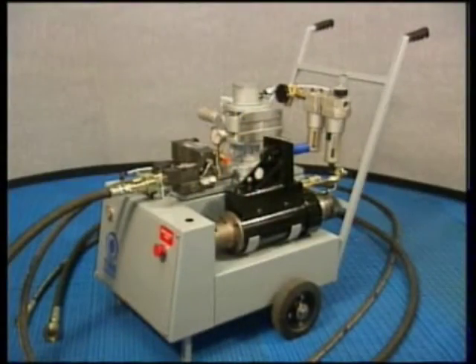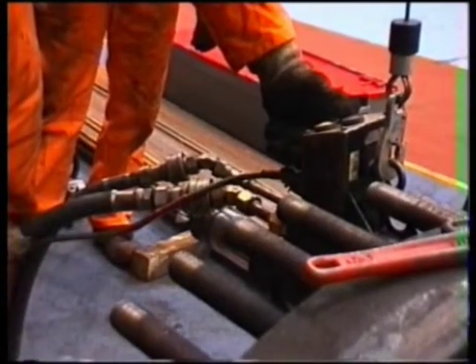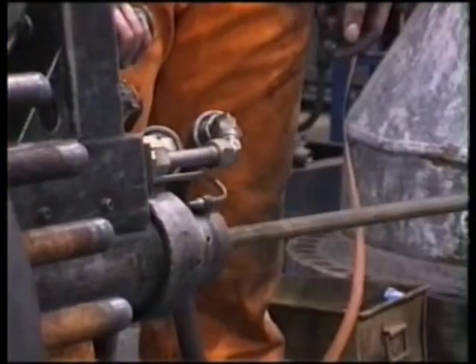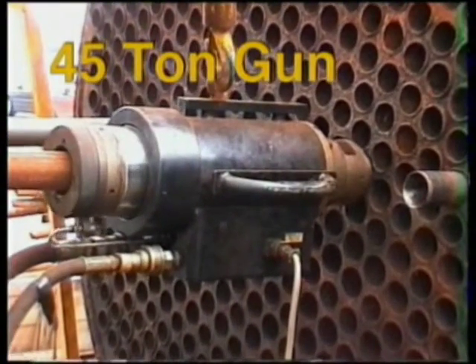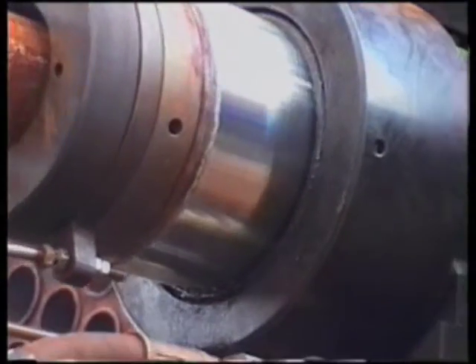The 15,000 series is supplied complete with quick release hose assemblies, a 24-volt control umbilical, and can be used with any of our range of pulling guns. The 15-ton gun for light-duty, high-speed work on tubes of outside diameters from 3/8 of an inch to 1 inch — for example, condenser work. The 30-ton gun for all tube sizes from outside diameters of 3/8 of an inch to 1 and a half inches continuously through the gun, and up to 3 inch stub pulling. The 45-ton gun for tube sizes up to 3 inches continuous through the gun, and for stub pulling applications on boilers and in steam drums.